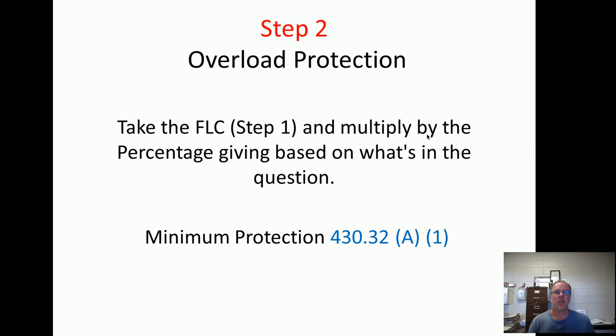Step two is the overload protection. The overload is what protects the motor; the breaker protects the wiring — that's steps three and four. Step two protects the motor. We want the motor to be able to start — you've got that inrush current, it takes a lot of amperage — but we don't want it to trip. The overloads allow it to start and maintain good ampacity, but we don't want it to get too hot. The biggest enemy is heat to a motor.